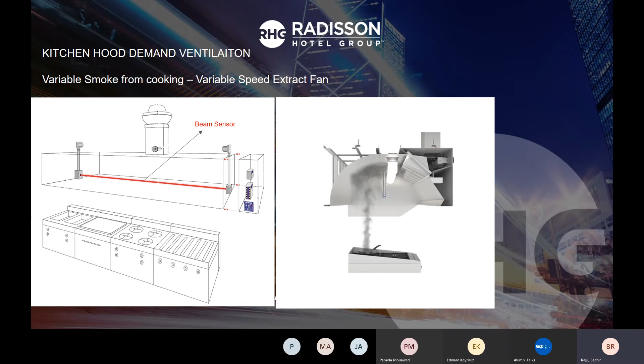Cool. Thank you. You're welcome. I will move forward to another example, which is similar to the kitchen demand ventilation. If we consider any restaurant or public area, as per the code, if we look at the table here, and consider, let's say, a cigar lounge or smoking lounge, it says that in the design you have to include 60 cubic feet per minute. It's a flow of fresh air and extract, a ventilation rate per person.